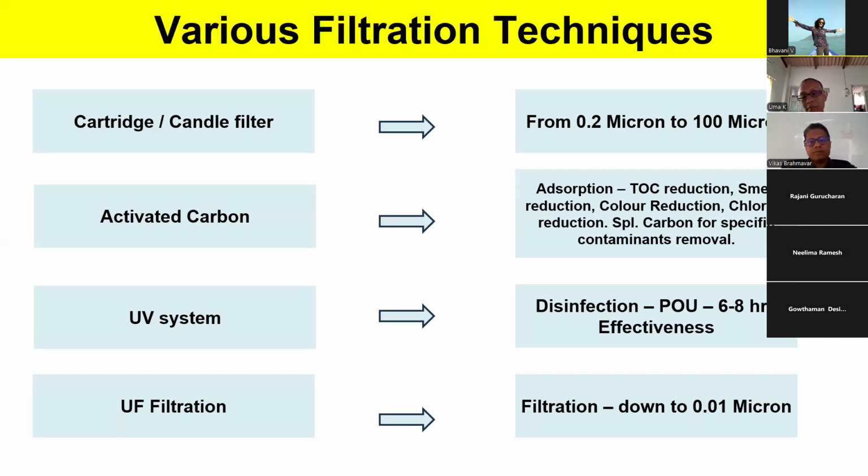At the Devanelli project, we use 900 to 1000 iodine value carbon, right? So higher adsorption: it will remove smell to a certain extent, color to a certain extent, and TOC, which is total organic contamination, just by adsorption. When water passes, it sits on these, and then you will need pressure to wash it back. So you do something called backwash and take all the contaminants out, right?